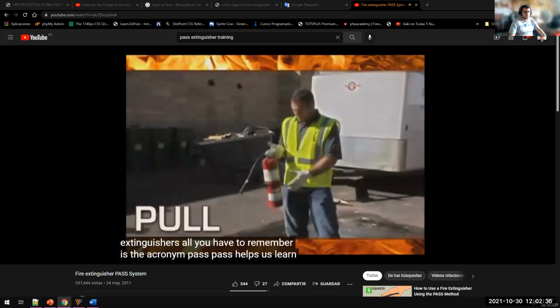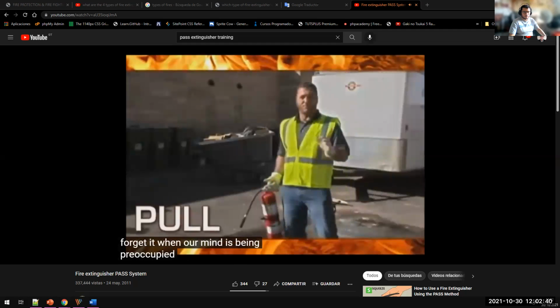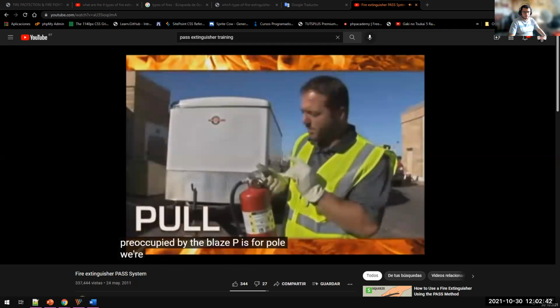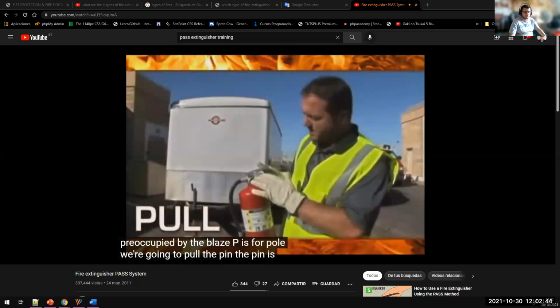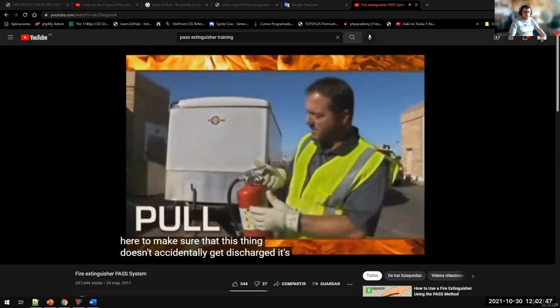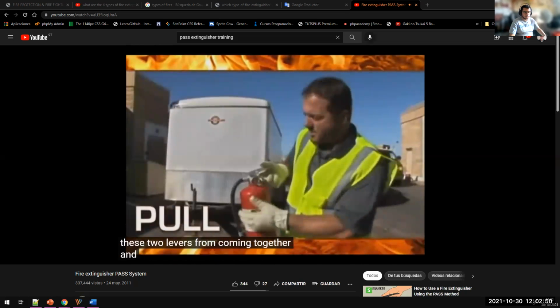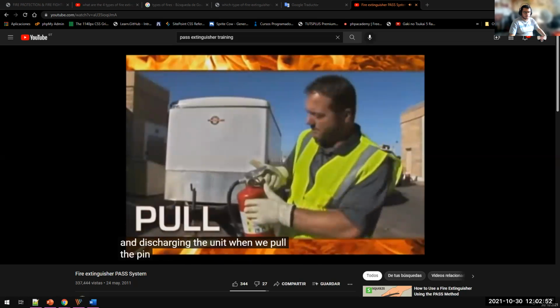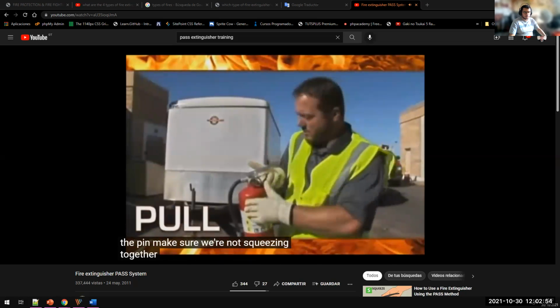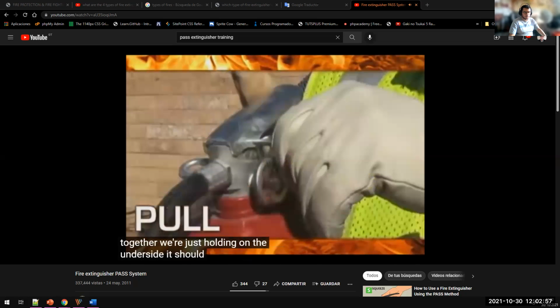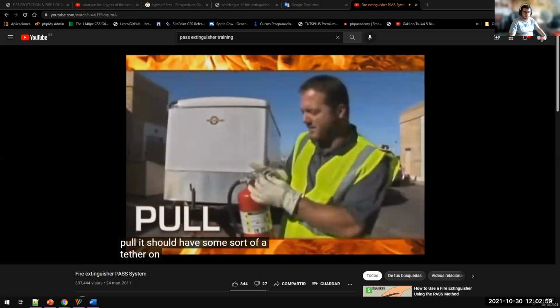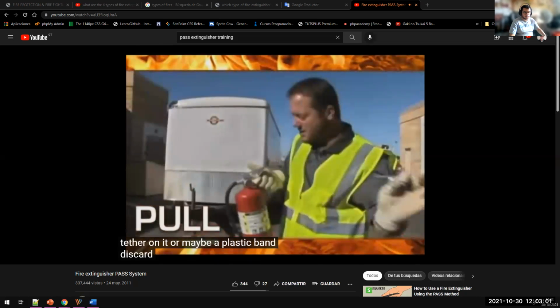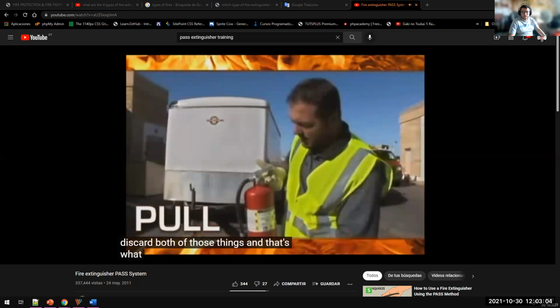PASS helps us learn how to use this thing safely and not forget it when our mind is being preoccupied by the blaze. P is for pull, and we're going to pull the pin. The pin is here to make sure that this thing doesn't accidentally get discharged. It's really the only thing that's stopping these two levers from coming together and discharging the unit. When we pull the pin, make sure we're not squeezing together. We're just holding on the underside. It should be pretty easy to pull. It should have some sort of a tether on it or maybe a plastic band. Discard both of those things.